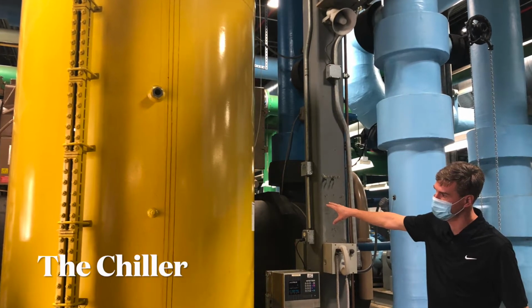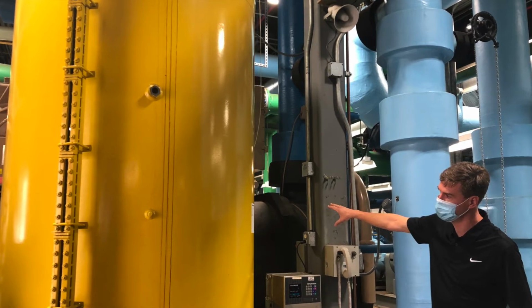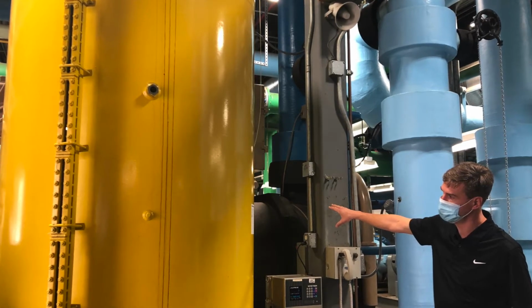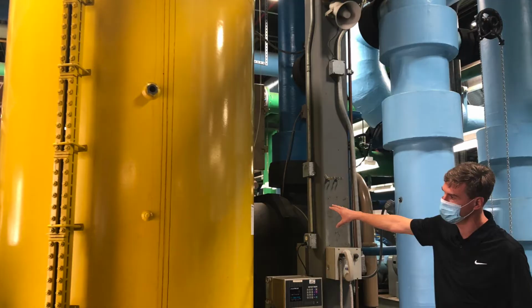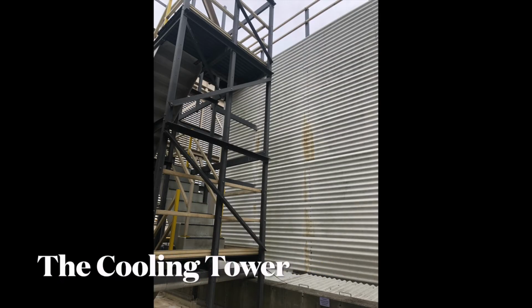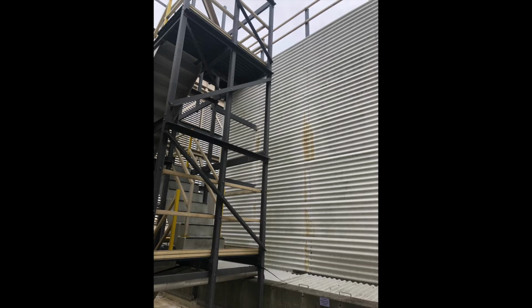The chiller appears in both the chilled water loop and the refrigerant cycle. It makes the chilled water cold, is located behind a large yellow container and holds an electric motor, which drives the creation of the cold water. Also, the cooling tower is found in the condenser water loop. The condenser water is brought up through a pipe and travels up to the top of the tower, and it spills down through the fill. As water trickles down, some of it evaporates, and that's how a cooling effect is created. Non-evaporated water trickles through the cooling tower and turns back down into the main room, which holds the chiller.